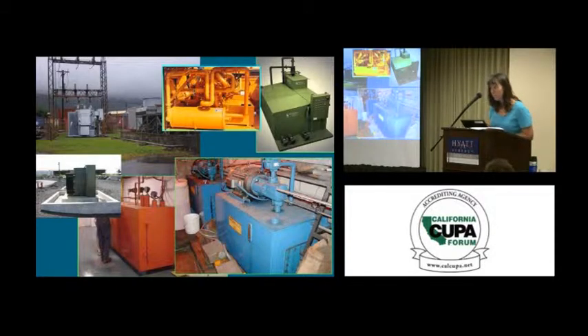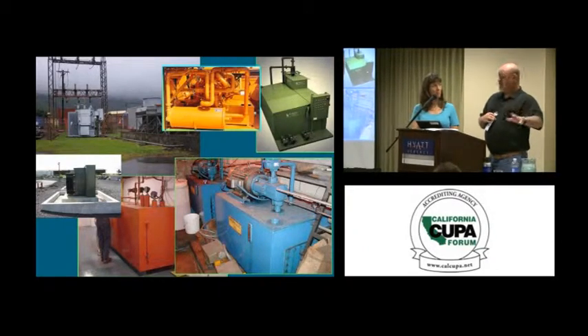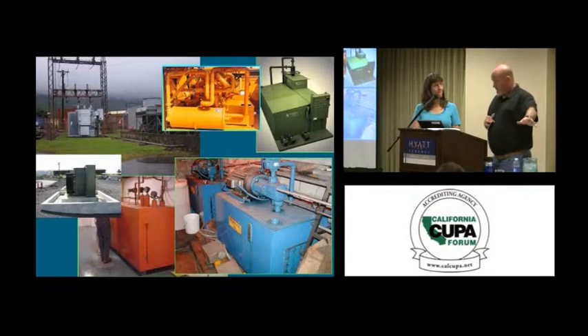Would elevators be considered oil-filled operational equipment? To get at your question, the reservoir system associated with an elevator, if its capacity is greater than 55 gallons, then yeah, it needs to be considered in the overall threshold determination for SPCC subjectivity. It may be that because it's a standalone system in a building, with the flexibility in defining a facility, you could say that could be identified as its own facility and therefore, if it's less than 1320, it could be stated as a facility that is below the threshold and therefore exempt.